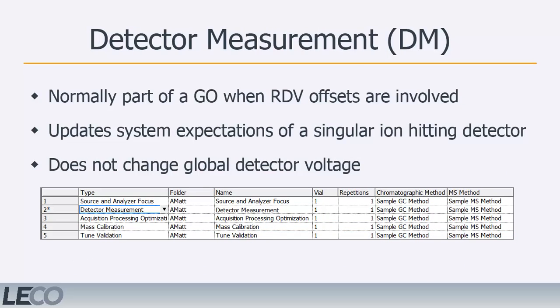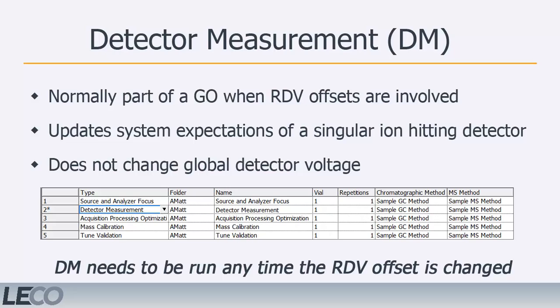A detector measurement, or DM, is automatically run during the gain optimization when a relative detector voltage offset exists in the current MS method. The detector measurement updates the system's expectations of the response from a single ion. The detector measurement does not change the global detector voltage set by the gain optimization. It only updates the system response at a given RDV offset. A detector measurement should be run independently of a GO anytime the RDV offset is changed within an MS method or if a different MS method with a non-zero voltage offset is used.